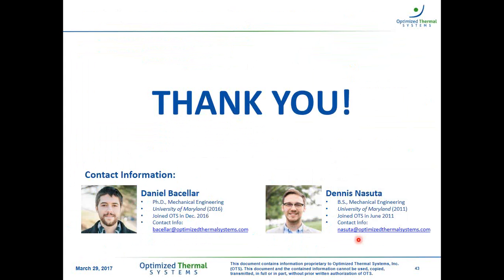But when we look at evaporators, we certainly have to consider the wet condition where the surface may be covered in a film of liquid. The new CFD-based correlations we've shown here are specifically developed for the dry condition. So we would expect that when we do experiments of evaporators in the wet condition, we would see some variation from the accumulation of condensation on the fin surfaces. We've done a few experiments with both 5 and 4 millimeter evaporators, and we've seen fairly good agreement with the predictions that the correlations give. But there is some discrepancy in terms of the sensible and latent heat load that requires some additional research. Nevertheless, I think the correlations are certainly valid for these types of heat exchangers as well.